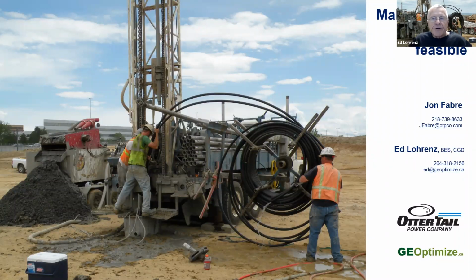of the building. And the reason for that is because most of the software out there, whether it's GLHEPro or Earth Energy Designer or whatever, or GLD, there's an assumption made for the duration of the peak loads. How many hours in a row are you going to have a peak cooling load or close to peak cooling load? If you're in something like a place with a lot of computers running all day long, that peak load might extend from about 8 or 9 in the morning to about 4 or 5 in the afternoon. In other situations, depending on the occupancy of the building, that peak load duration may only be an hour or two. So that's the big thing that varies in running it with monthly or hourly loads. But when we're doing the final design, we'll run the hourly loads just to confirm what we found using the monthly loads, simply because it's quicker to model it using monthly loads.